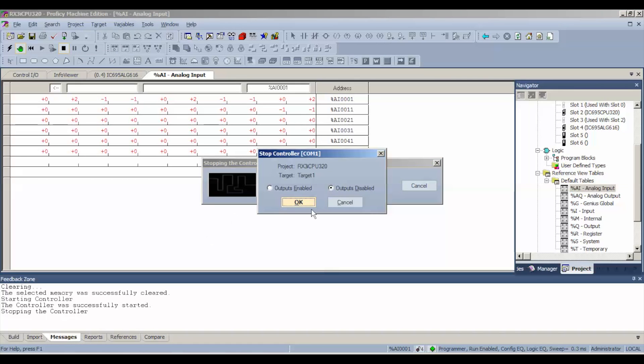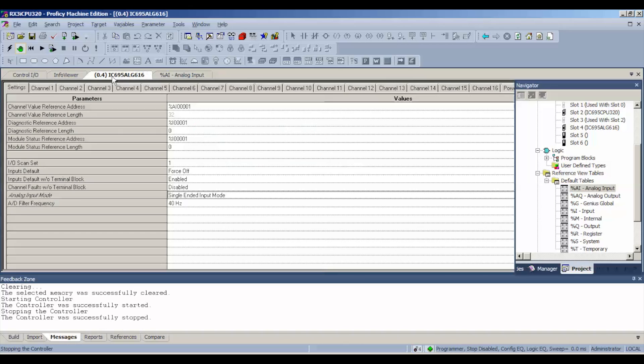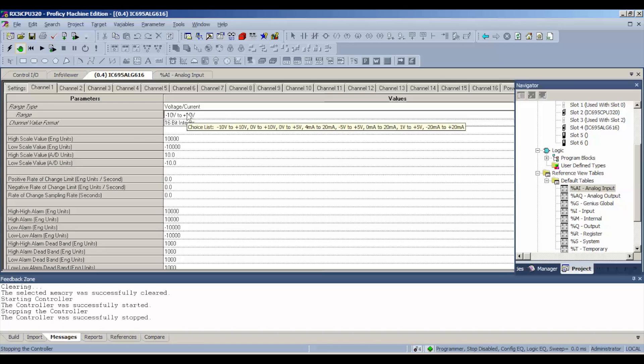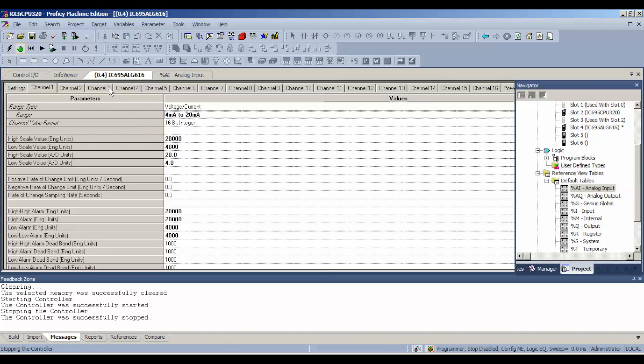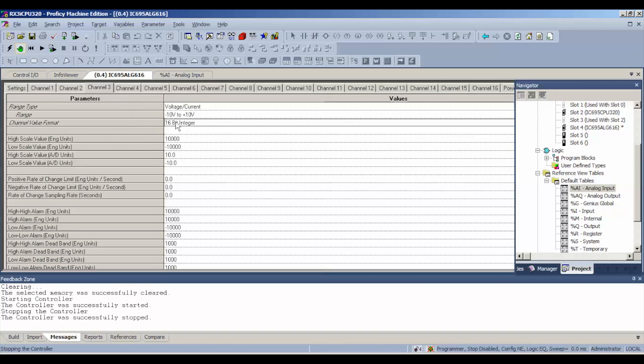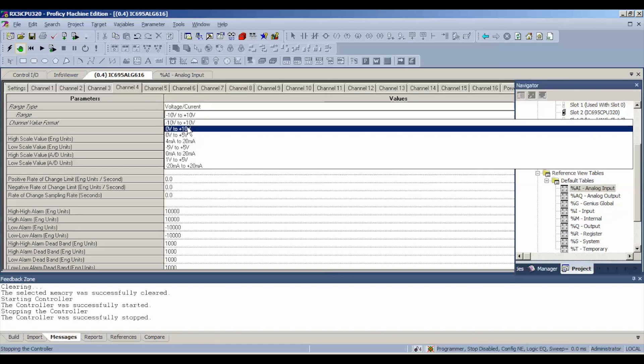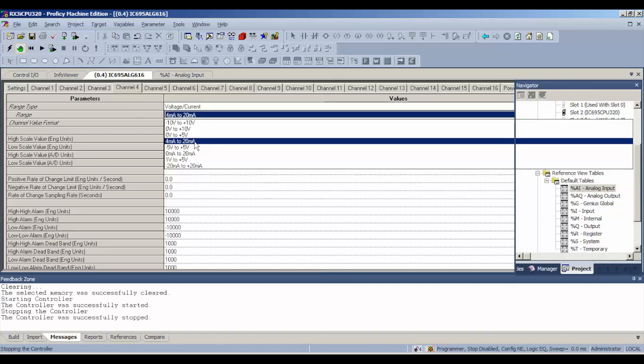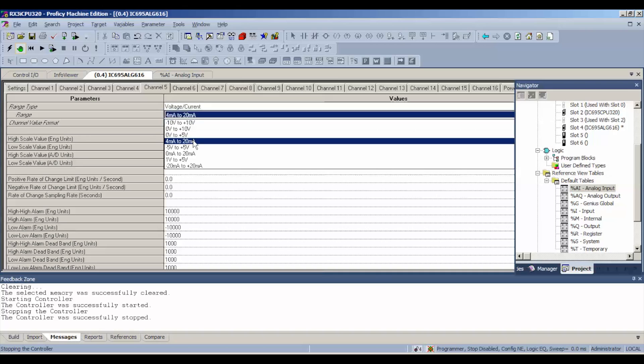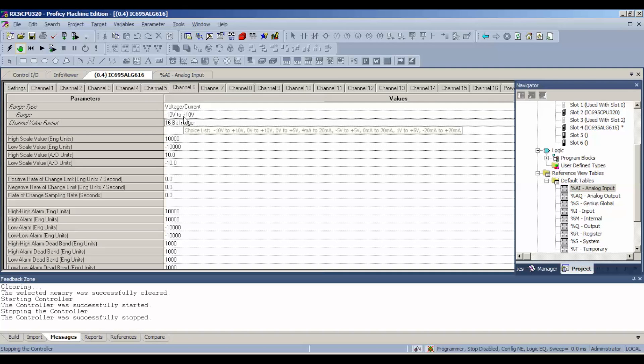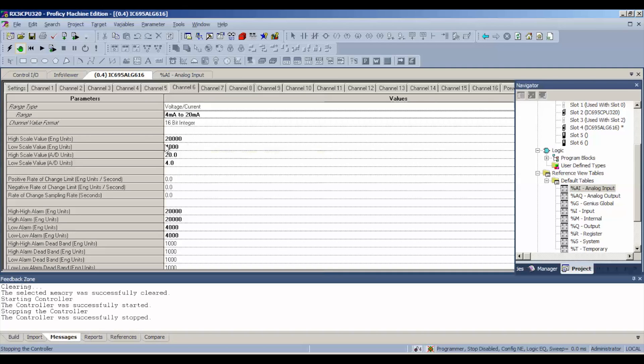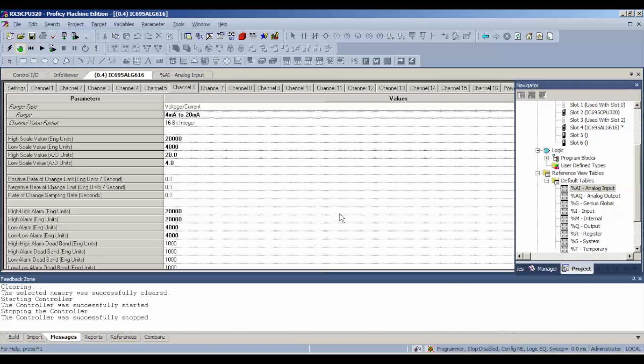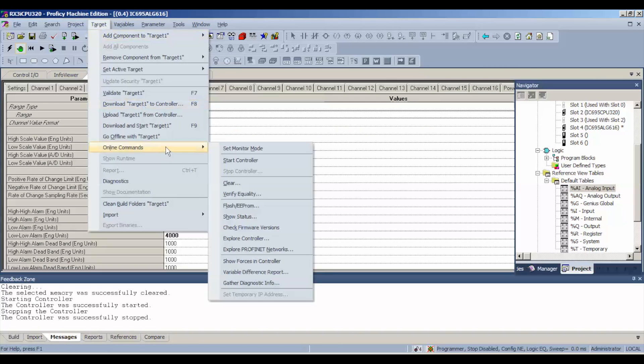Now that we've tested voltage, I'm going to stop the controller. Go back to our tab, slot number four, ALG 616, channel one, and I'm just going to simply switch it to four to 20 milliamp. You can use zero to 20 milliamp if that's something you need or something you have. I happen to have a four to 20 milliamp generator, so that's what I'm going to use. Again, I'm just going to do the first six channels, just as an example. Now pay attention down below. What's the status we're in? We're stopped, we're disabled, our configuration is not equal anymore. Again, this is just a slight difference. We're just asking it to check milliamp, but it can see the difference. It knows that it's different and it's going to fault you.